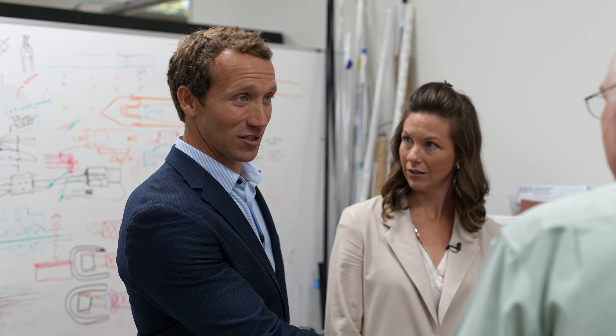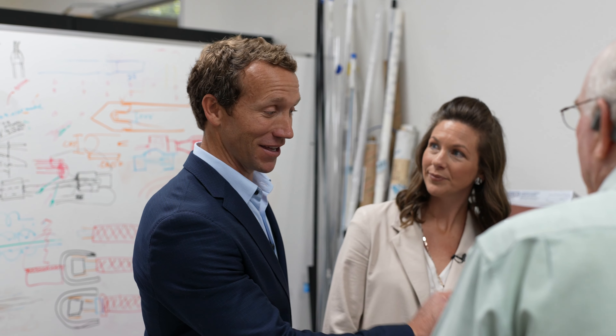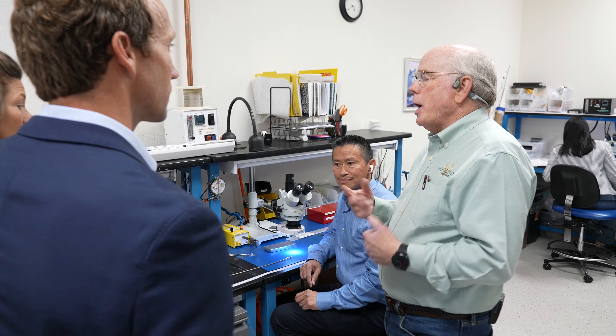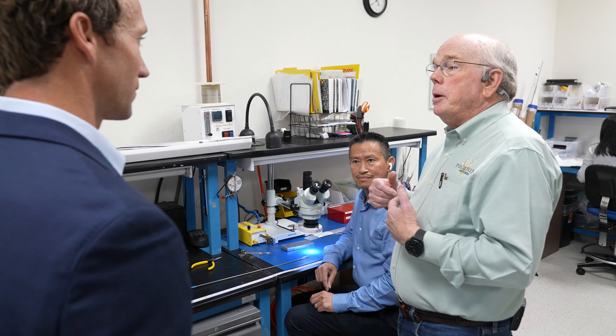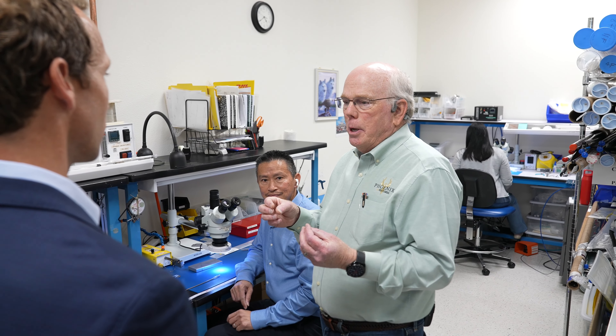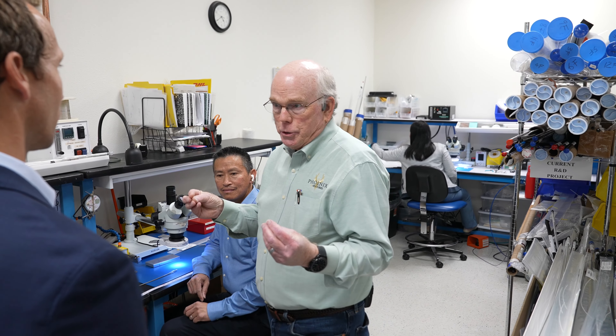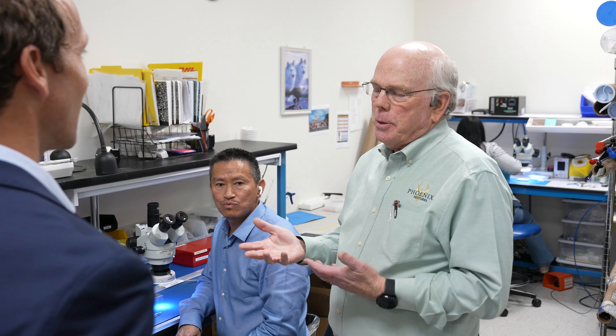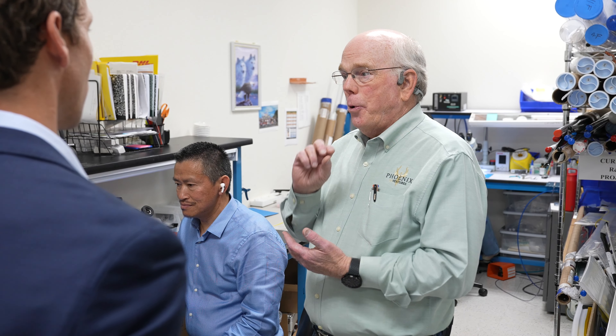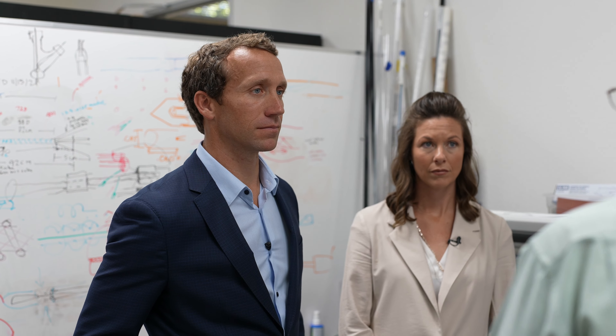So obviously this is R&D space right here. This is not going in a human. Could you build this catheter once you refined it here and actually build it to go into a human? Excellent question. Here we would prove ideas, test them on a bench model to see that this can deploy in the vasculature. Maybe we model it in polymeric tubing. And once we have something performing adequately, then we go through all the rigors of testing, documentation, following all the requirements of standards and regulatory agencies such as ISO standards and FDA requirements.